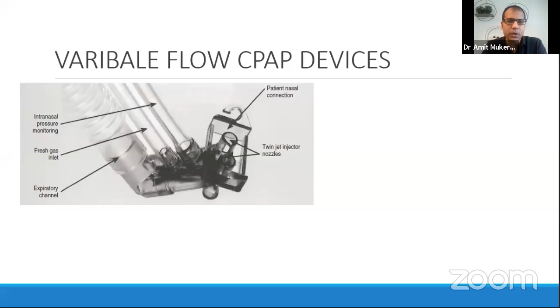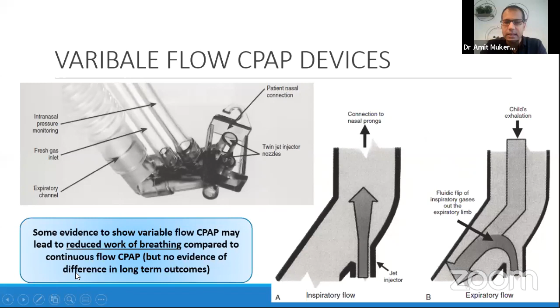And what's unique about the variable flow CPAP devices is that during inhalation, the gas flow will push the gas towards the patient interface. Whereas during exhalation, when the baby is breathing out, the gas flow will actually revert over and go towards the expiratory column. So when the child's breathing out, you don't have this flow of gas going towards the baby. There's a mechanism behind that called the Coanda effect, and you can read about this in more detail. But it intuitively makes sense, and it's supported by evidence that these variable flow CPAP devices may lead to reduced work of breathing compared to a continuous flow device. But again, there's no evidence of any differences in long-term outcomes.